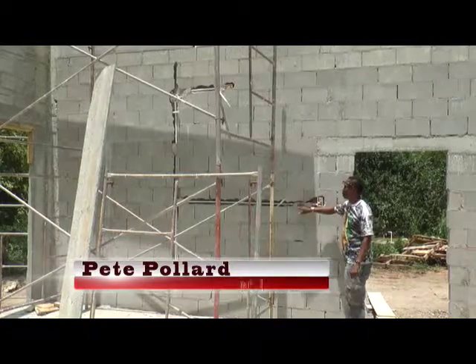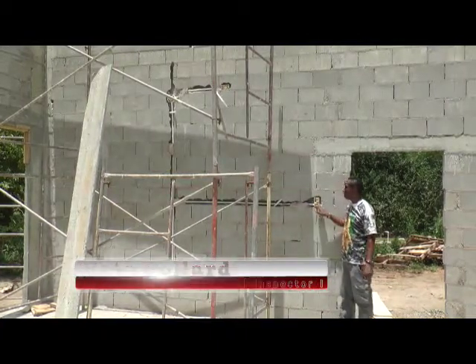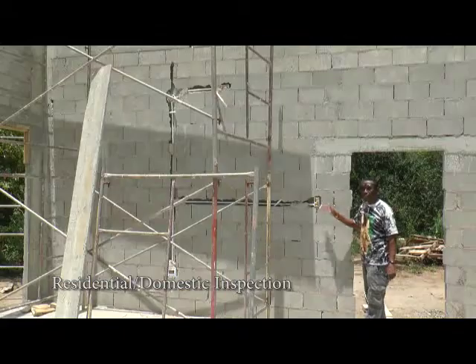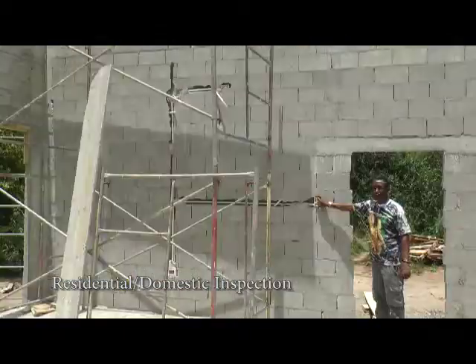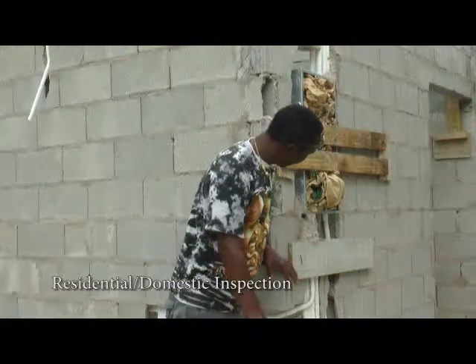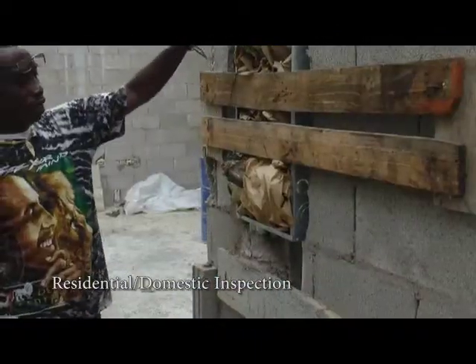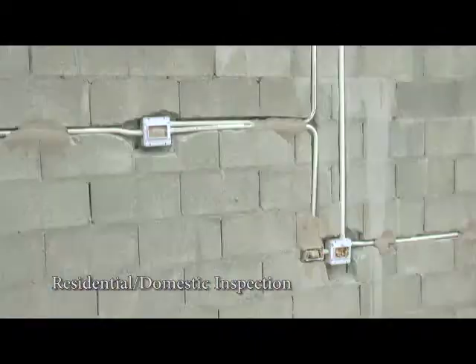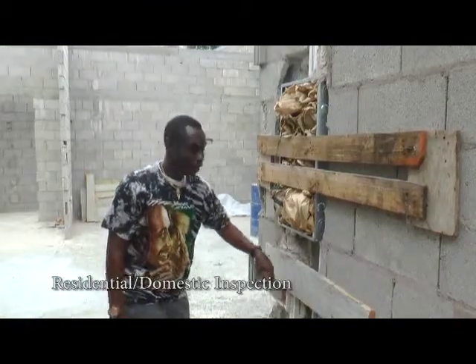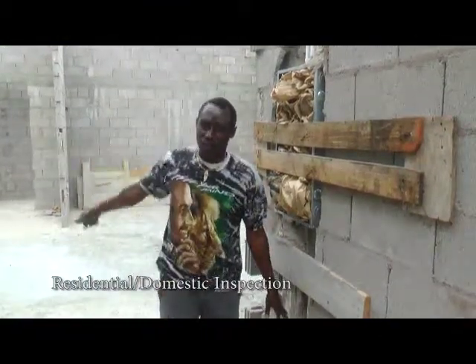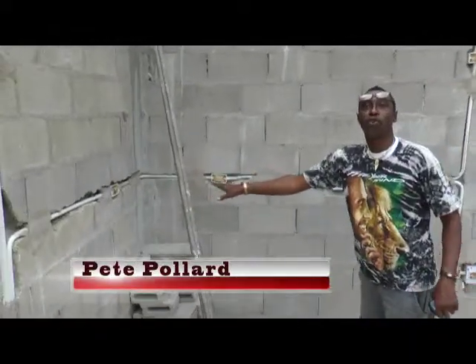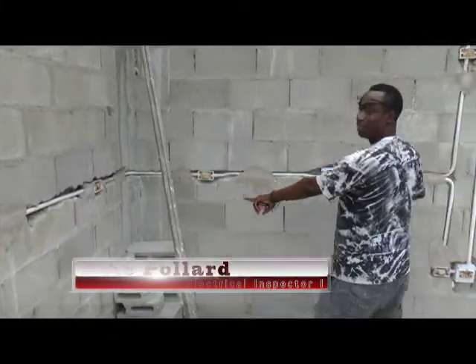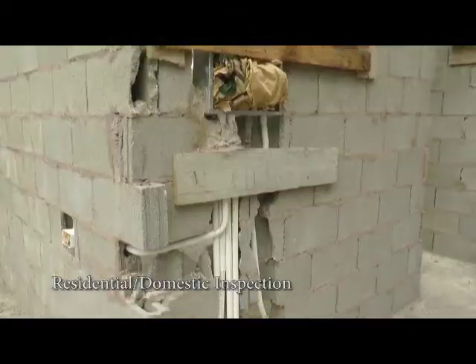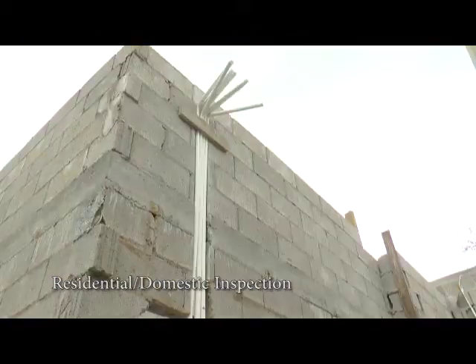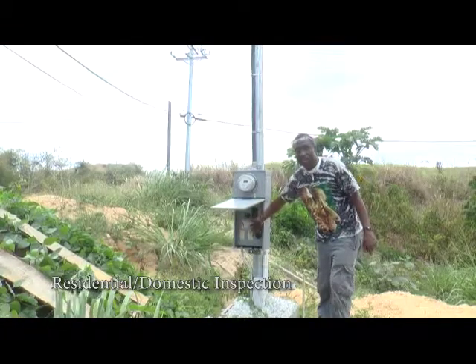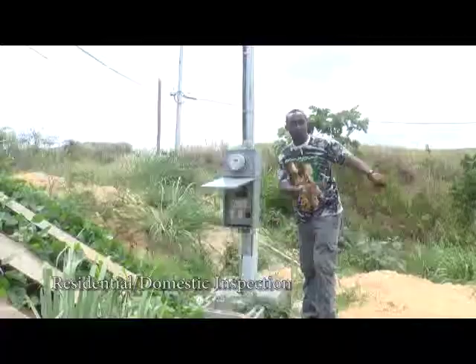You don't expect it to have your pipes in and your boxes in without stabilizing it. Because when the guys come to plaster, it must not interfere with the box. You want the panel where everybody could be accessible to it. All the conduits must come into here and distribute to all the walls. Plugs, counter height, above your counter. Everything is connected back to the panel. You have outlets here so that they could do their work.